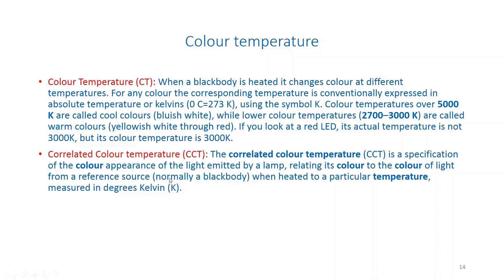Correlated color temperature (CCT) is the color appearance of light emitted by a lamp. If a light source is a true blackbody, its chromaticity coordinates fall on the blackbody curve. If not, it falls outside, but you can still correlate it to a blackbody temperature using isothermal lines perpendicular to the blackbody curve. The CCT of a source is the temperature of the isothermal line it falls closest to.